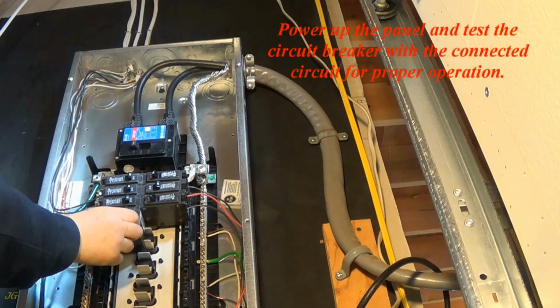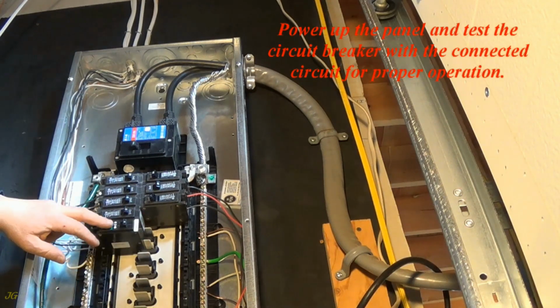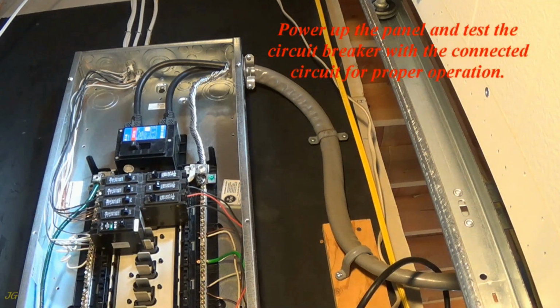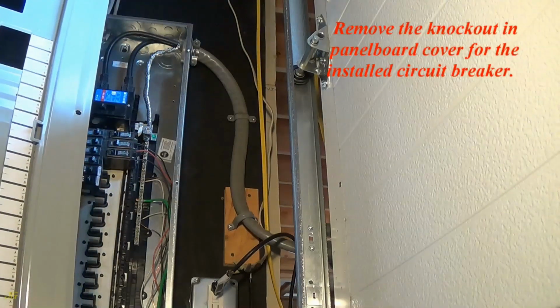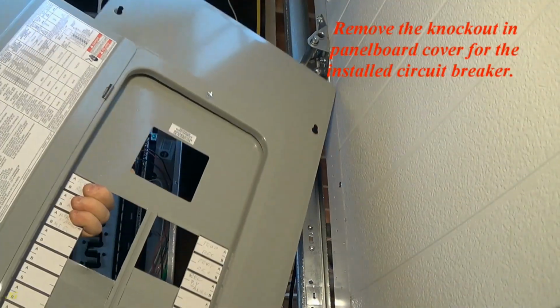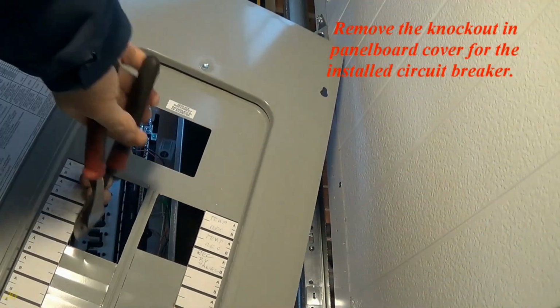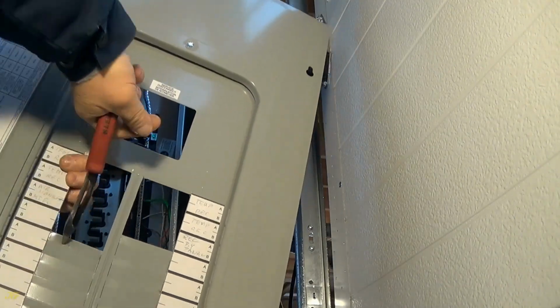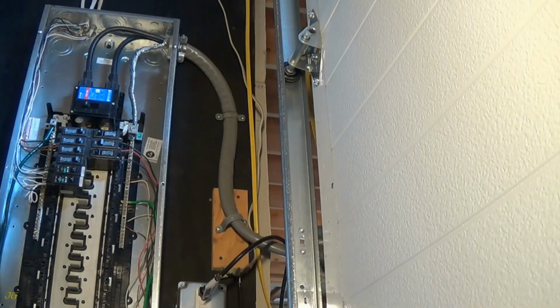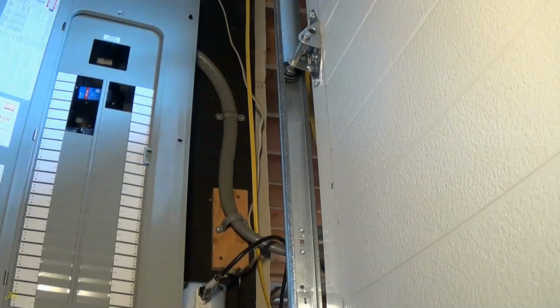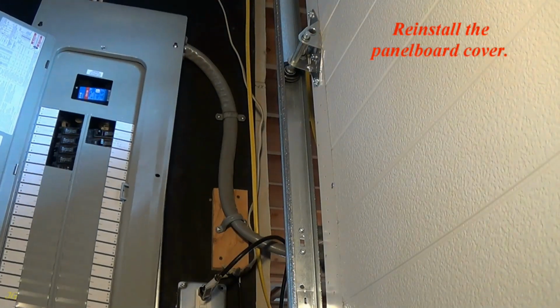Power up the panel and test the circuit breaker with the connected circuit for proper operation. Remove the knockout in panelboard cover for the installed circuit breaker. Reinstall the panel board cover.